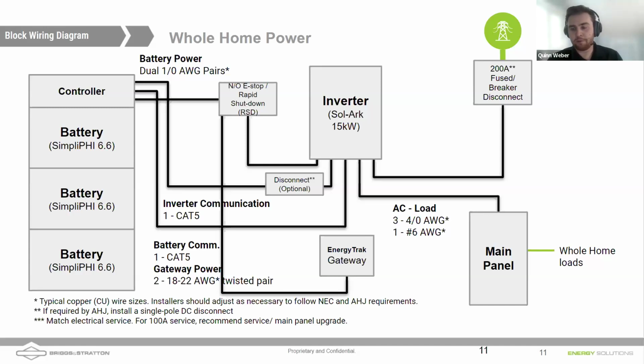So if you've installed a Sol-Ark 15K, you may have been using PCS controls and not really known about it. It's an additional certification that our inverter has. But with having that certification, the advantage here is that we don't have to limit that connection using breakers anymore. We can use full. Yep. Exactly. There's no limit on the breakers. You can control it through software rather than hardware.